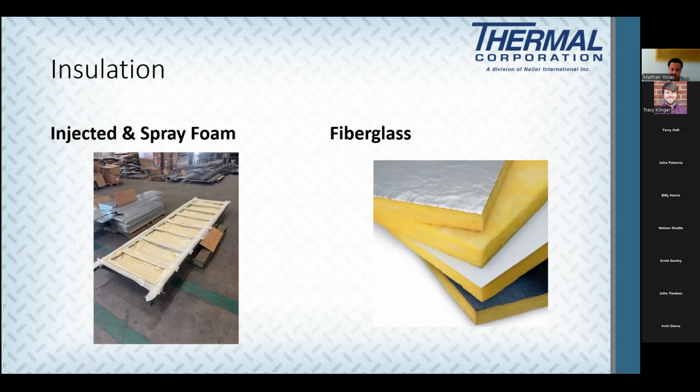So say you had a two-inch construction unit, you want a good R value, so you go with foam insulation, but the fan is where the most sound is going to be, so you're worried about that. You can add in that section, just on top of those 2-inch panels, and then you'll have 3 inches in that section: 2 inches of foam with your inner and outer liners. You're always doing double wall construction nowadays, so you'll add on top of your inner liner 1 inch of fiberglass insulation with perforated sheet metal on top of it to help with the sound attenuation in that section.